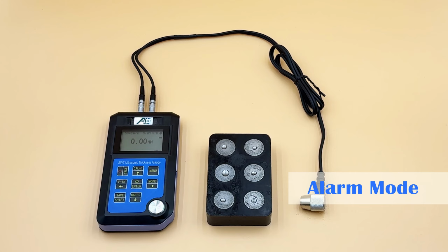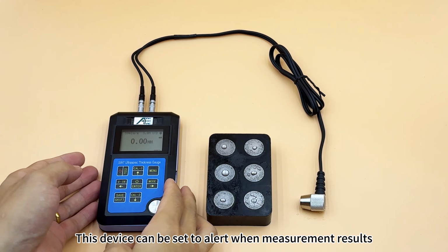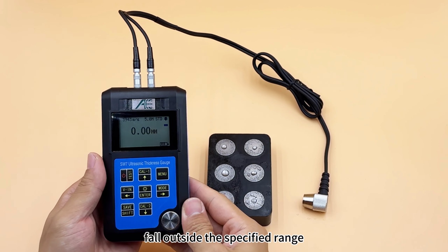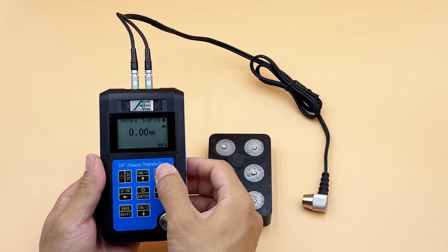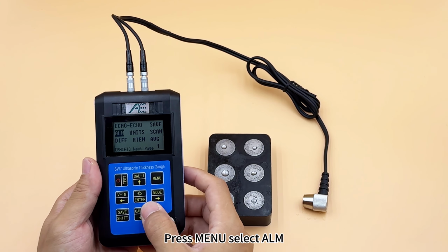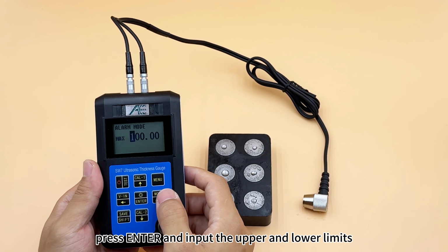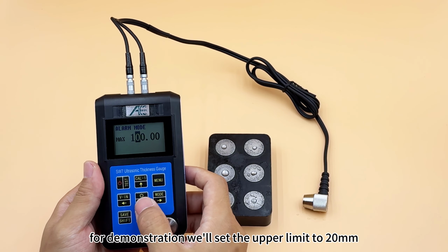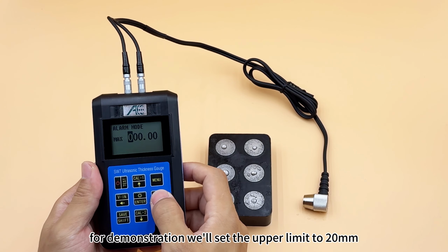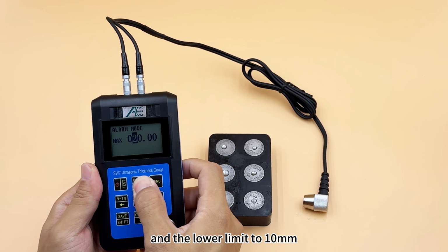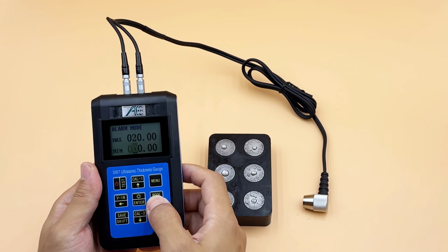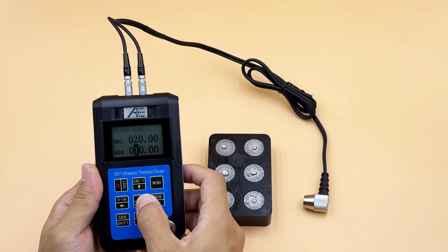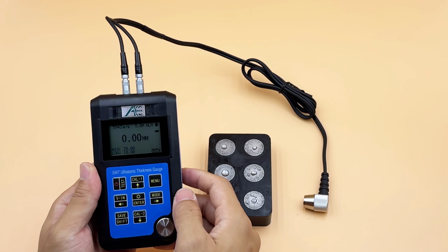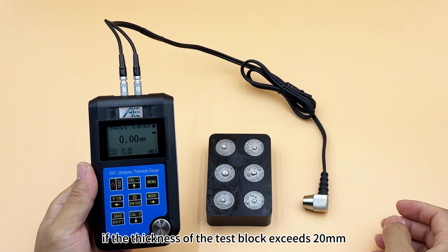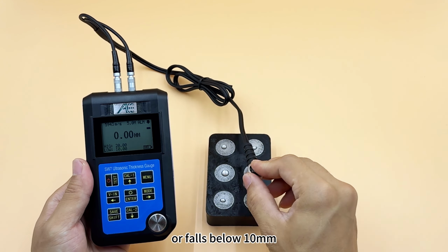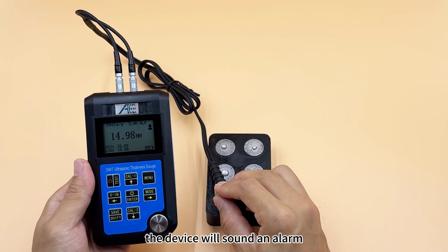Alarm mode. This device can be set to alert when measurement results fall outside the specified range. Press Menu, select ALM, press Enter, and input the upper and lower limits. For demonstration, we'll set the upper limit to 20 mm and the lower limit to 10 mm, then press Enter. Press Test. If the thickness of the test block exceeds 20 mm or falls below 10 mm, the device will sound an alarm.